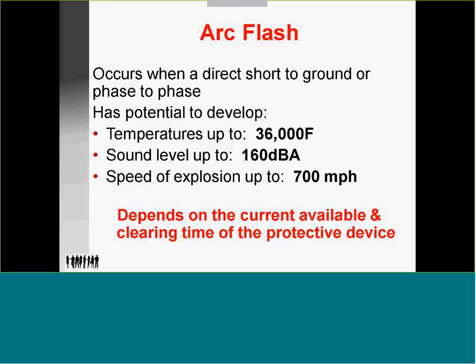So the arc is taking place, and the temperature goes higher. The highest one ever recorded was 36,000 degrees so far, and it caused significant damage in a short amount of time. Again, fault current is coming in off the grid. When you start a short, the utility sees your company beginning to take more power, so it sends more there. Now, it would be several microseconds, up to a cycle, 2 cycles, 3 cycles. Then it realizes it's too much, and the safety device kicks in and trips it out.